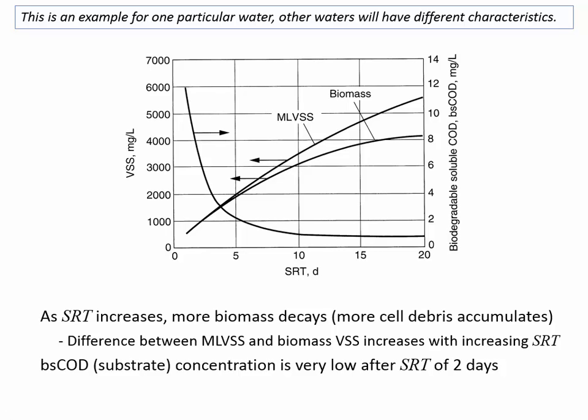The longer you're recycling it over and over and over again, there's going to be a lot of dead cells in there. And so the dead cells aren't removing substrate, but still they're requiring you to pump them, and it's increasing the volume of sludge in the system. So there's a balance to be had. You don't want the system to be too big because it's costly, but having a big system enables you to have really good performance. And so what we're trying to do is, somewhere on this line, it's diminishing returns.